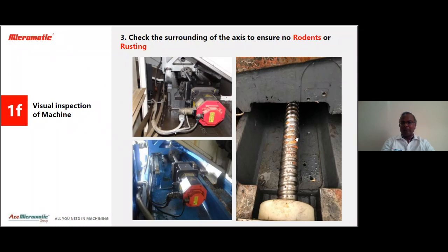You may be aware that when metal parts are exposed to air, the possibility of rusting definitely increases. One of the photos we have shown in the presentation is rusting of a ball screw. Ball screw rusting can be removed using kerosene, petrol or WD-40, which is also available in the field. You can apply it and remove the rusting. You must ensure that there is no rusting on the ball screw. One more photo we have shown here is the Fanuc motor and power cable. There also we need to check properly for any damage caused by rodents or rats.